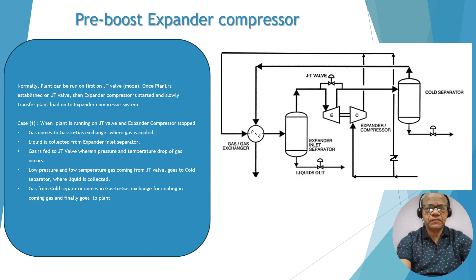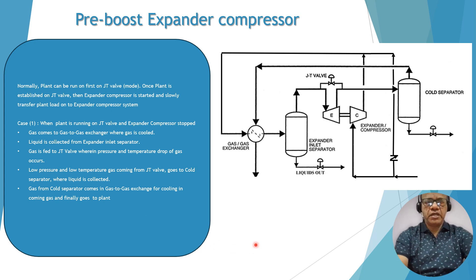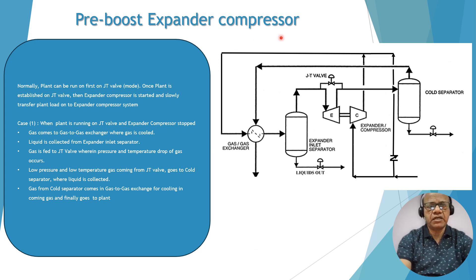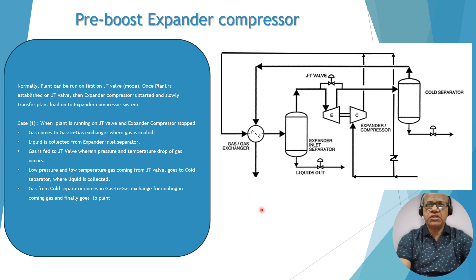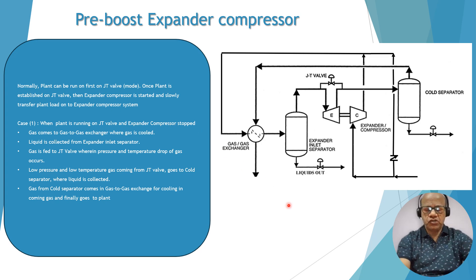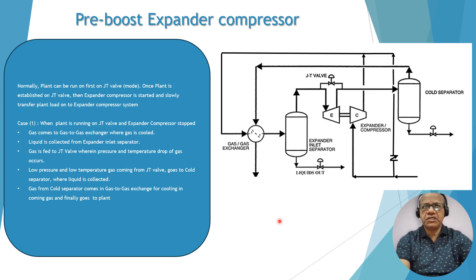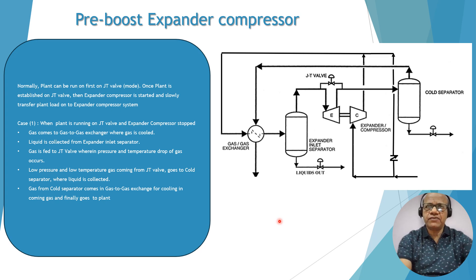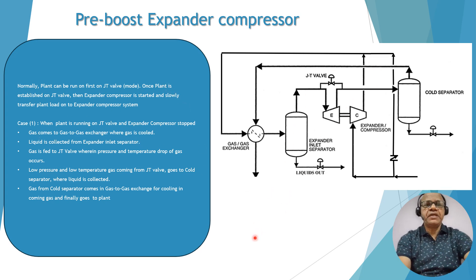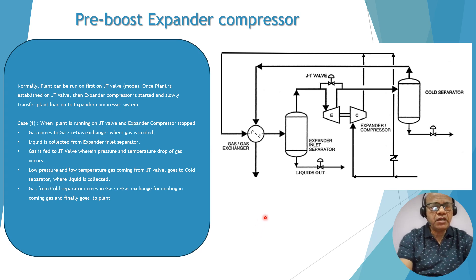This is the basic path of the turbo expander. Now, what is a pre-boost expander compressor? The turbo expander is also called an expander compressor. In the pre-boost arrangement, this can be explained in two cases. Case one: when the machine is not running and the plant is running on JT mode. First, the plant is started on JT mode without starting the turbo expander. Once the plant is stabilized and the required differential pressure across the JT is achieved, we start the turbo expander compressor and then slowly the plant load is transferred from JT to turbo expander.